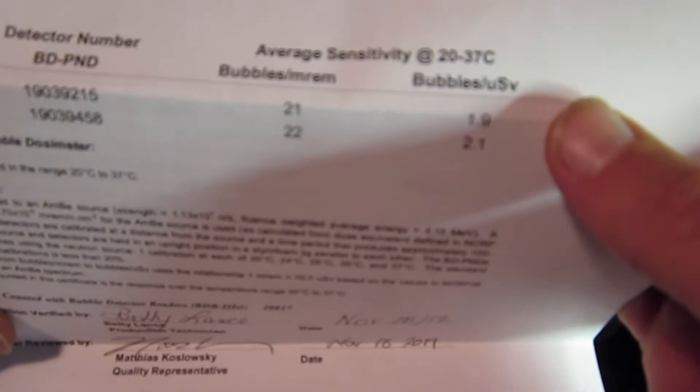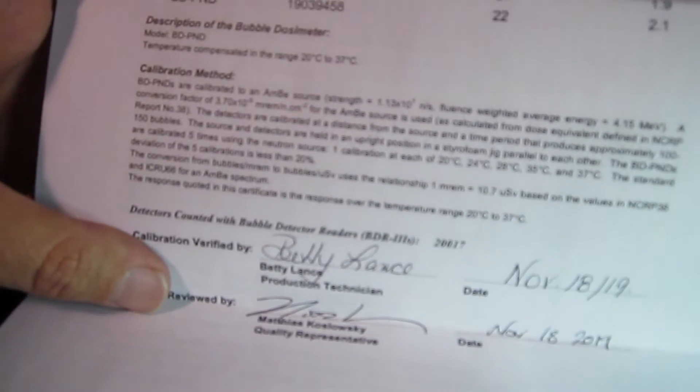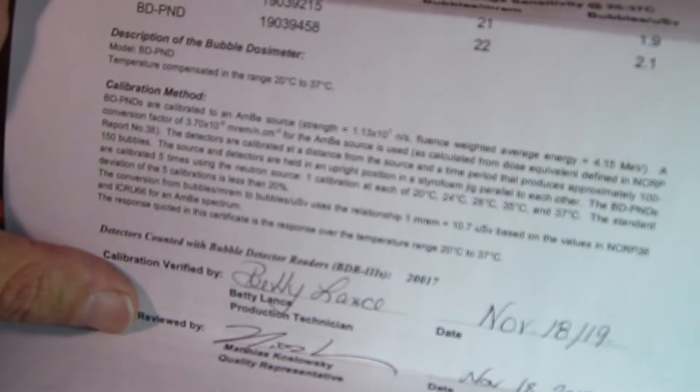It looks like they sent me an envelope with a calibration certificate. Bubbles per millirem — it looks like it's about 21 bubbles per mrem. And it has it in Sv. BDPN — there are the serial numbers on it. It looks like they used an americium-beryllium source to calibrate it. They give you the flux: 1.13 times 10 to the 7 neutrons per second, and the energy of the neutrons. Very interesting.